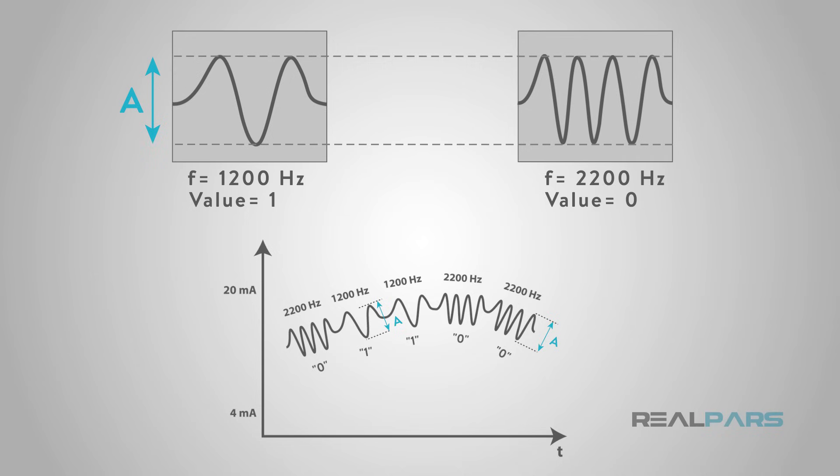The net effect of the sine wave is then 0, so the analog value of the sensor measurement data is not affected by the HART signal, just as a telephone voice conversation is not affected by the caller ID signal using the same Bell 202 protocol.